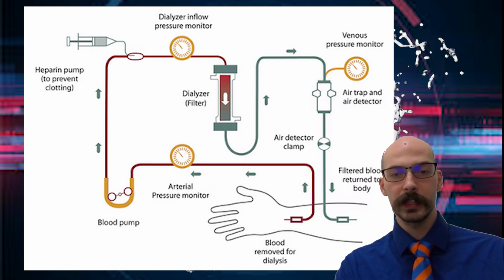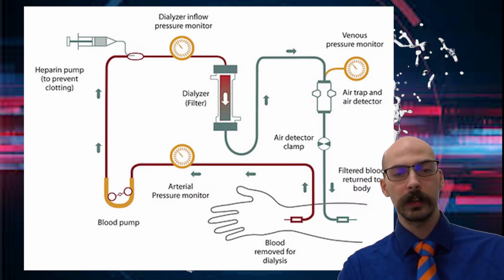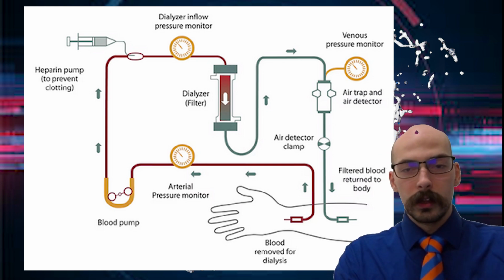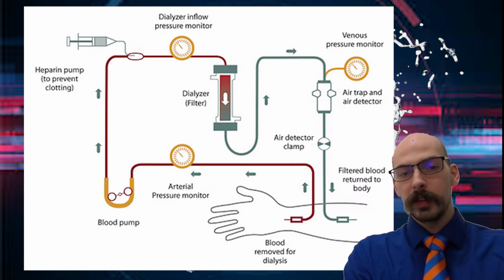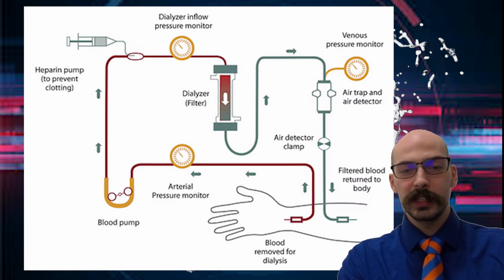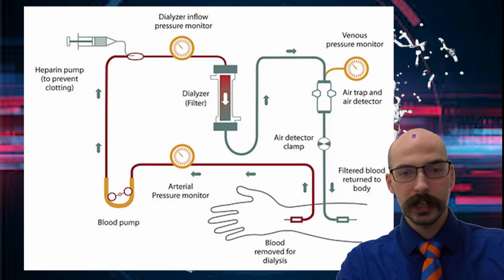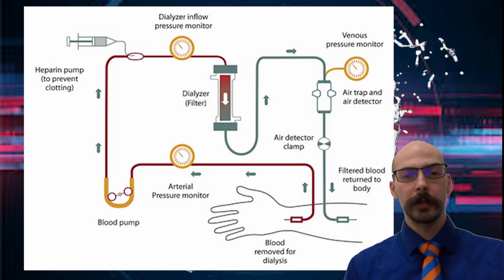Traditionally, dialysis uses hollow fiber technology, which requires a long flow path and higher blood flow rate and has limitations for home dialysis. Flat plates can be more suitable for home dialysis due to their potentially lower blood flow requirements and more compact design. Naturally, the next step from home dialysis is artificial kidneys.